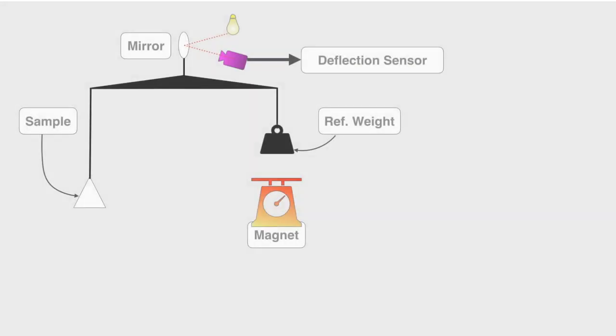The instrumentation of TGA is consisting of the following components. First and the most important is the balance. It must be highly sensitive analytical balance. It must be precise and accurate at experimental temperature.